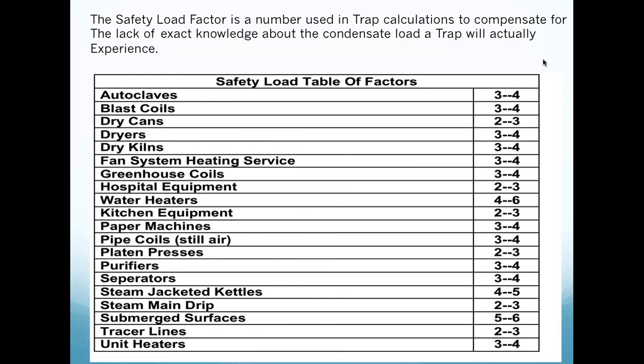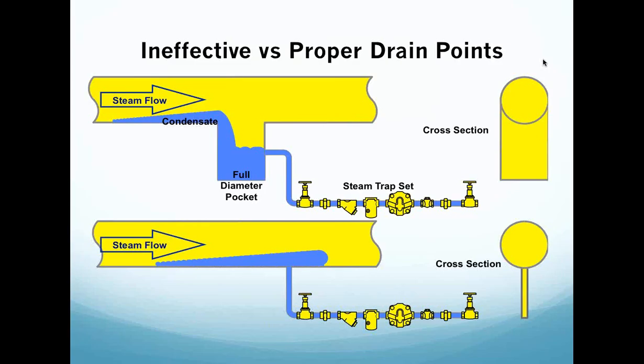The safety load factor, once we look at sizing a steam trap application, is nothing more than a number to compensate for the lack of exact knowledge about condensate loads that a trap will actually experience. So what it does is it covers our fanny, gives us the ability to make sure that we get a trap that will work.